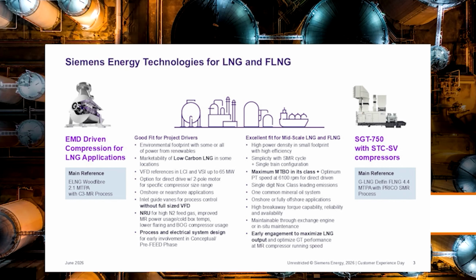Contrasting that, we have gas turbine driven compression. So our SGT-750 is the main driver on reference project Delfin for floating LNG. It's designed for 4.4 million tons per annum with the single mixed refrigerant process by PRICO by Black & Veatch. And in general, gas turbines have been sort of the bread and butter for LNG projects. To date, there were a couple of steam turbine driven ones, maybe back in the late 60s and 70s, but everything else has been driven by gas turbines.